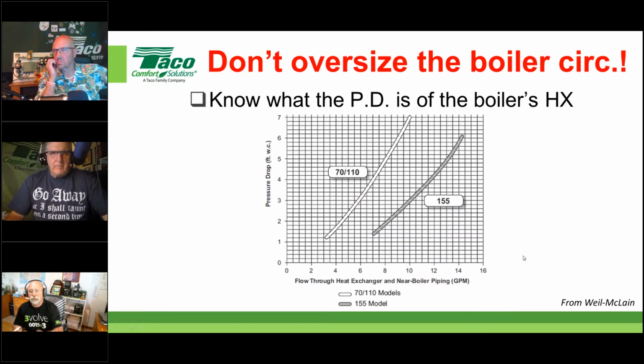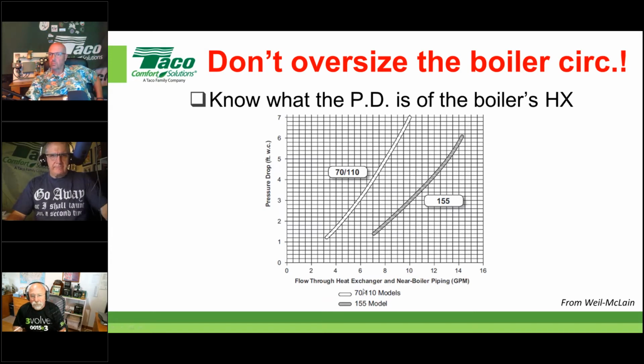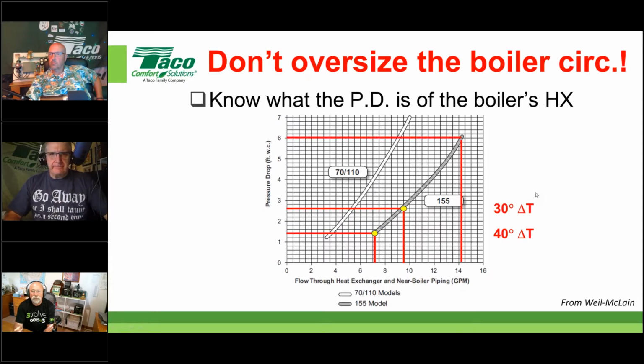One thing about this particular chart that's a little different than others is that Weil-McLain puts a little bit of extra fudge factor in there. That means the resultant pressure drop for the flow through the heat exchanger includes some incidental near-boiler piping, maybe some fittings. So make sure you understand that they've already included that, so you don't need to double dip, and I'll show you what we're talking about in a second. But for the sake of time, let's just show you that same range: a 40, a 30, and a 20-degree delta T. So notice that, even with the pipe, valves and fittings and everything, they're saying it's around 6 feet of head, is all.